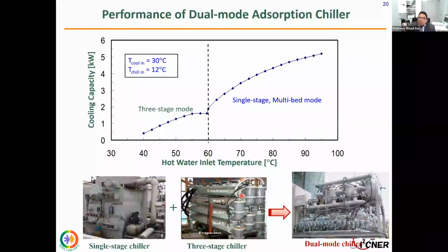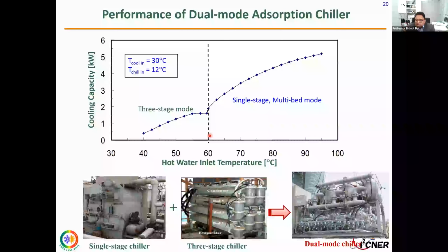So what is the benefit of doing all this? The benefit is like this. We also developed one dual mode cycle, combining the single stage cycle and the 3-stage cycle. As you can see here, if you use solar energy, for example, as our heat source, and it is a sunny day, of course we'll use it as a single stage cycle like this one, and we can get cooling capacity. If it is a 5 kilowatt capacity, we can get about 5 kilowatt after 80 degree heat source temperature. But if the temperature of the heat source becomes below 60 degree, it is very difficult to run the single stage cycle, but the 3-stage cycle can operate, and it can give you a cooling capacity of 2 kilowatt. And we make a dual mode cycle by combining these two cycles.